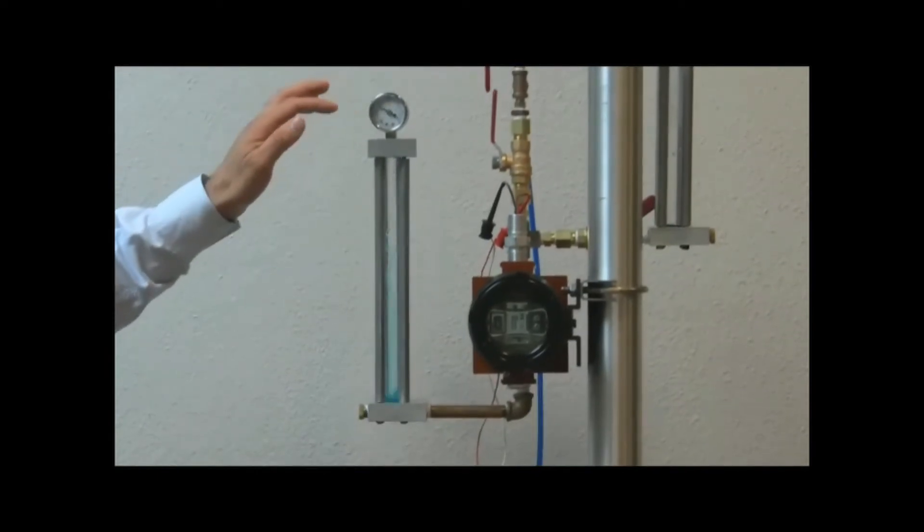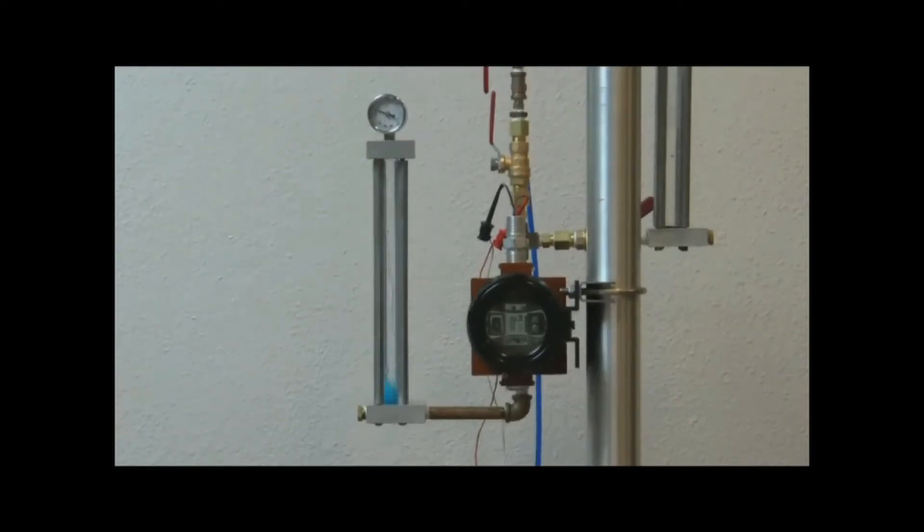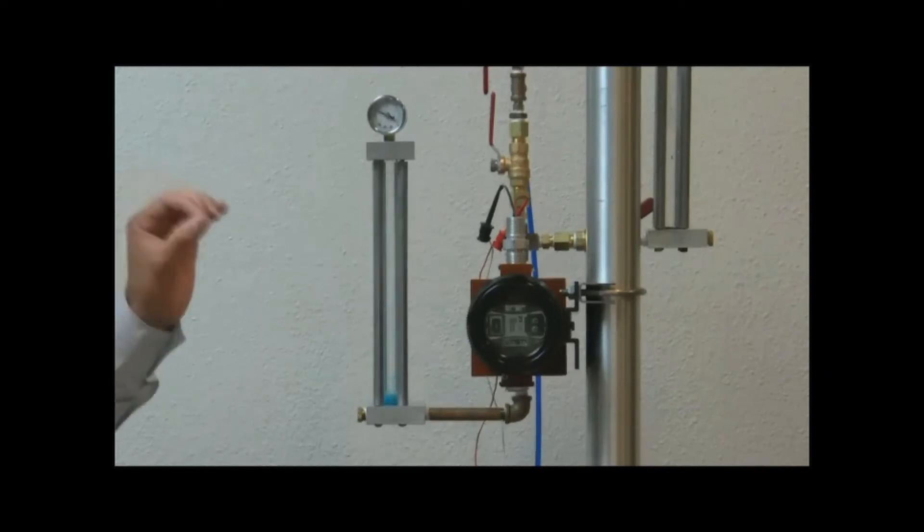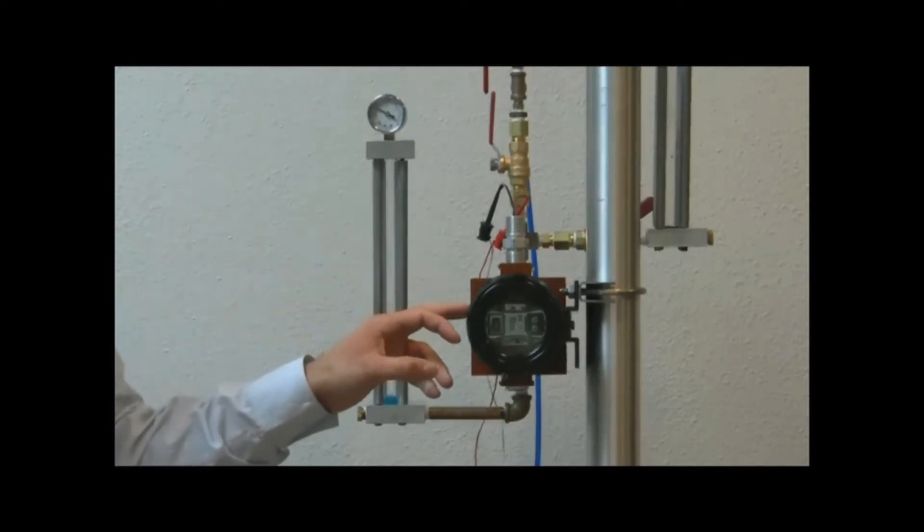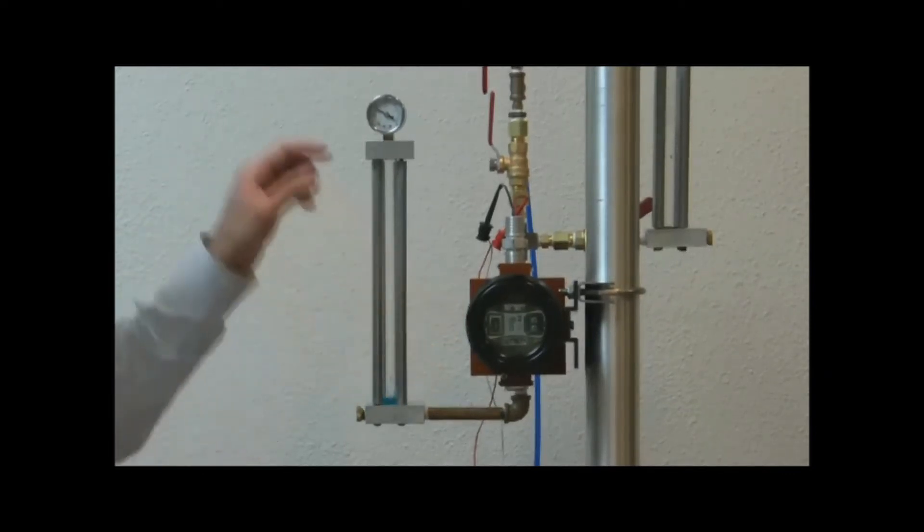As you can see, the slug temporarily disrupts the output. However, once the liquid is cleared away from the internal gas passages in the unit, the output returns to normal.